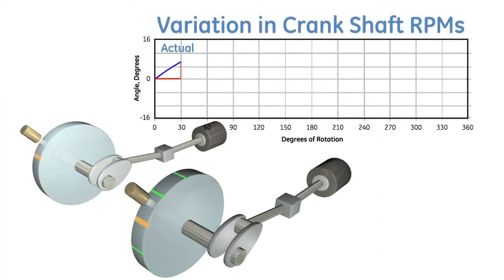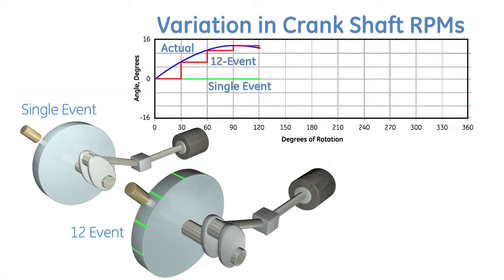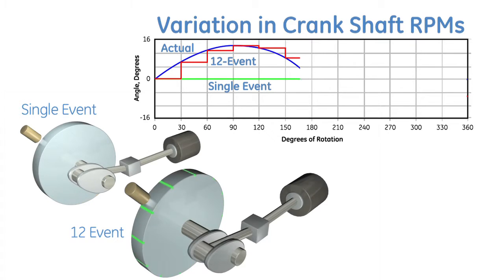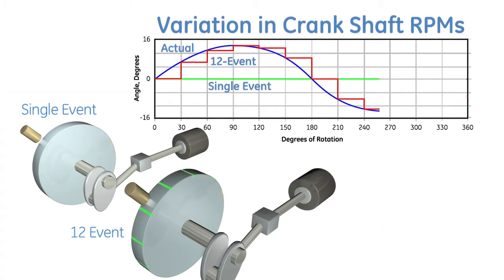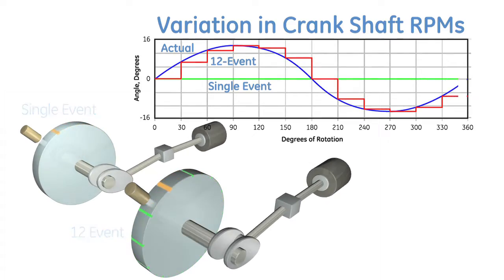In reality, they should be comparing our multi-event wheel with their single event. The 12 events allows us to better determine changes in angular velocity of the crankshaft and therefore more accurately characterize compressor conditions throughout the entire cycle.